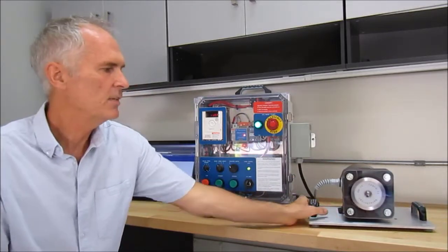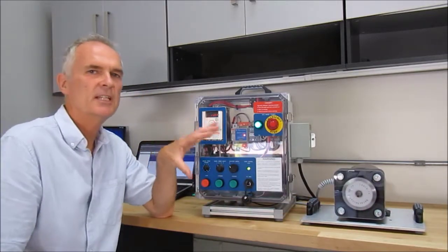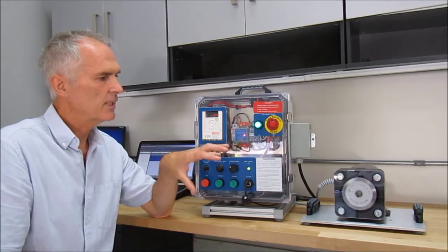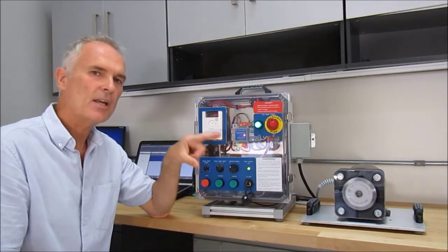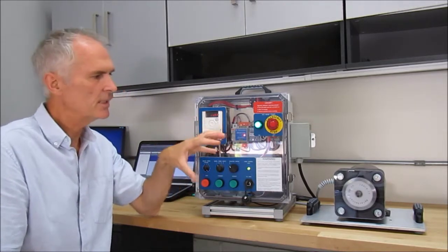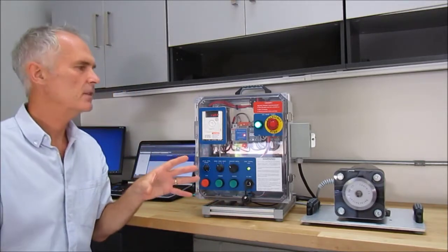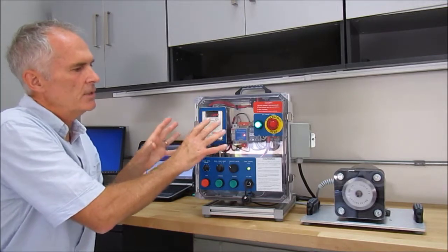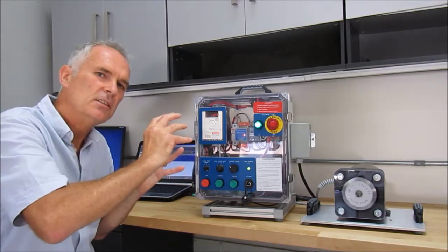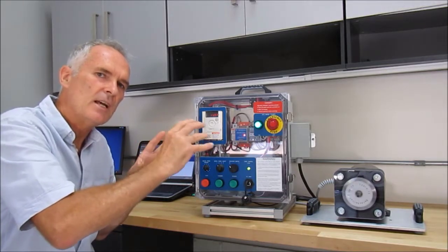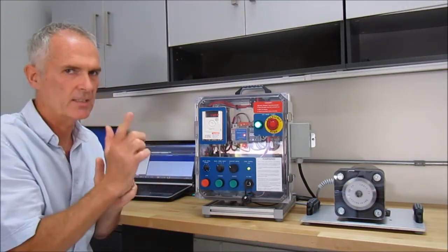It's very important that you enter the correct current value so that the drive can protect the motor from a sustained overload. Okay, so that again, very, very important. The drive will use the current value that you enter from that nameplate to protect that motor. If you know the actual running current of the motor, you can go into the drive and run it and monitor the current, and if you know the load is fixed, you can actually even adjust that current to a closer value to protect the motor, and it's called the motor thermal current protection. And we are going to get into that in our training.